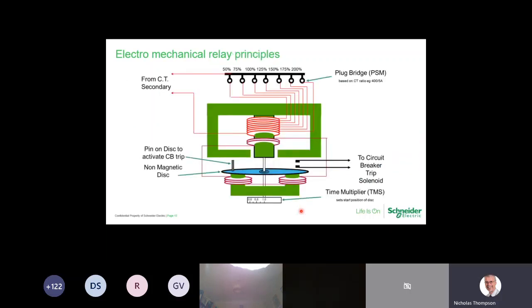When we look at the relay in a little bit closer detail here, we've got your CT, the secondary side of your CT, coming in. We've got what's called a plug bridge, so you can change the sensitivity of the relay depending on where the plugs go. We've got coils, we've got a disc with a peg, and the key is the peg. The peg is fixed on the disc, which will rotate given a certain amount of current. The disc is held back with a spring, and the principle is the higher the current, the quicker the disc is going to move, and ultimately if the peg reaches the contacts here, then the peg will short out the circuit and the circuit breaker will then trip. What we've got down at the bottom here is our time multiplier disc, and we can change the time multiplier up or down.